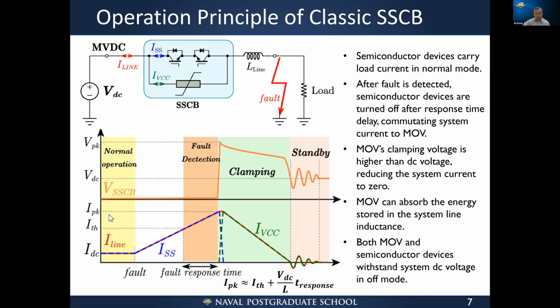So in normal operation, the devices are turned on to carry the current, right? The load current will just flow through the solid state semiconductor devices, and the voltage across the solid state circuit breaker is almost 0, right? At this point, a fault occurs. And then, because the load had been bypassed, the DC bus voltage will all be across the inductance. Of course, the current will increase rapidly.